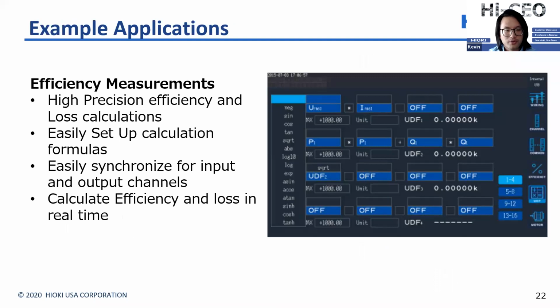Another thing I would like to go over is the efficiency calculations. When measuring, for example, DC-AC converter efficiencies, accuracy is required not only for AC, but also for DC. The accuracy of both the PW6001 and the 3390 allows us to make accurate and stable efficiency measurements. You're also able to set up equations on the power analyzers to compute measurement values however you want and get your results in real time.